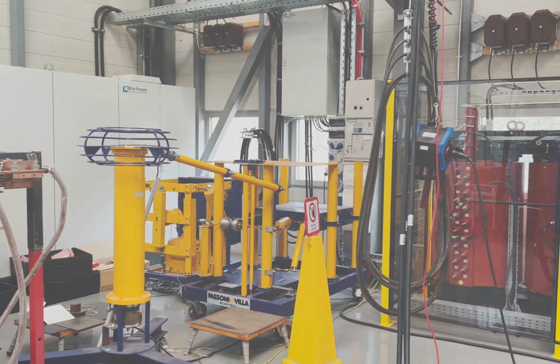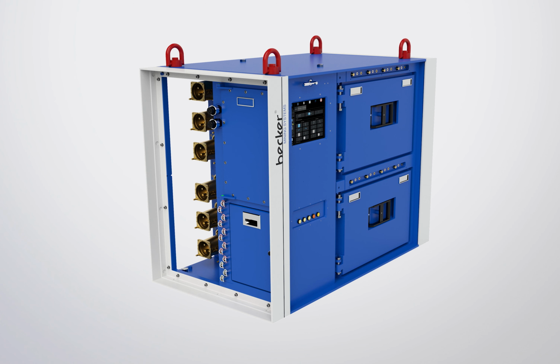Currently, we are testing the new features of the remote control of the new compact station CS4008. The CS4008 is a 1 kV to 4.16 kV disconnecting circuit breaker with 8 internal slots. We perform integration tests of these components such as the internal field bus, PLC, and slide-in module. We also test the human interface via our explosion-proof 15-inch graphic display. Profibus field bus is tested as well. Some of the functionality tests we perform are earth fault lockouts, pilot circuit, pilot with machine recognition, motor temperature monitoring circuits, and more. The remote control monitoring is connected via Ethernet.